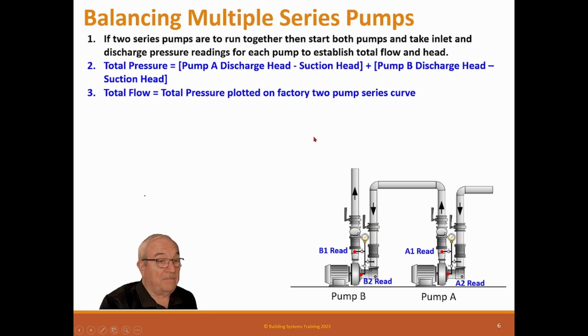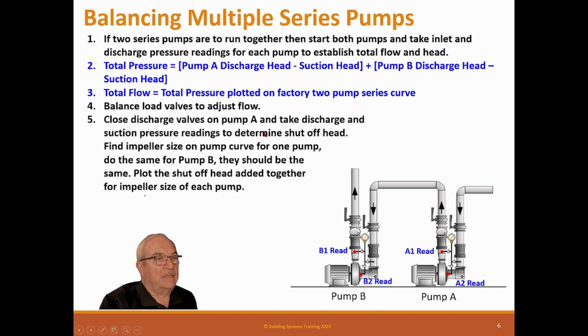So this is the same. You have to get a 2-pump series curve to tell where you're really at. And then you go balance the load just like always. And then you need to find the impellers, and you have to do each one of these separately to find the impeller. So you just close off this one and read the discharge and suction, and then close off this one and read the suction. You need to figure out where you're at, and then you do the impellers with the pumps.